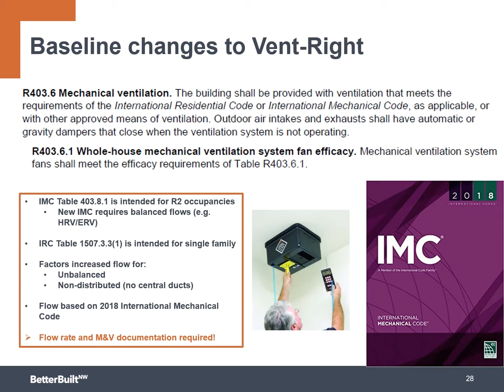Again, the flow rates are based on the 2018 International Mechanical Code. And flow rates and M&V documentation, there's a certificate we'll talk about later and actually show you how to fill out, is required per the state codes. Your jurisdiction may actually require that to be tested by a third party as well. But at the very minimum, the flow rate and the M&V documentation is going to be required by your jurisdiction.